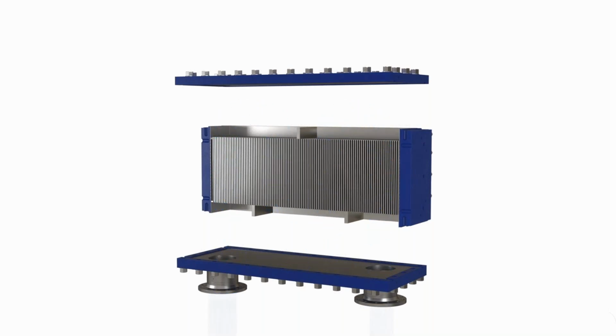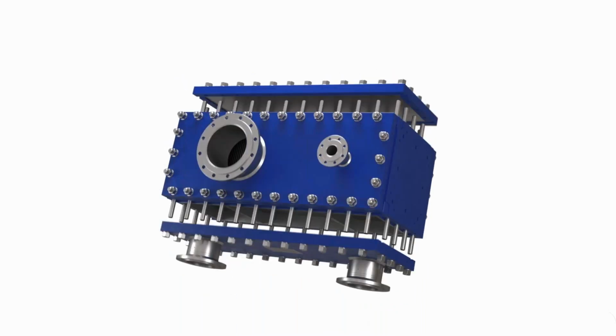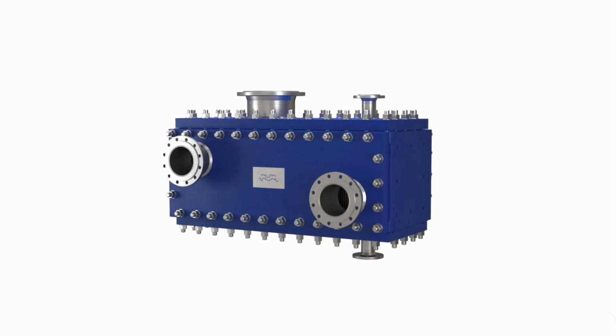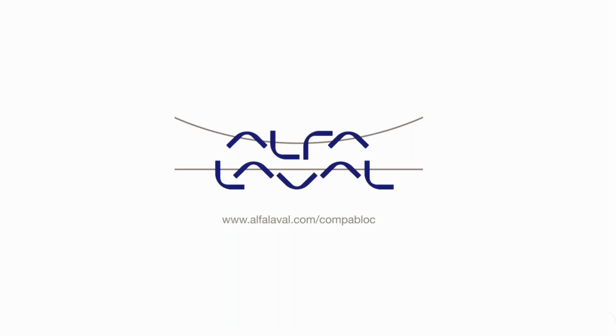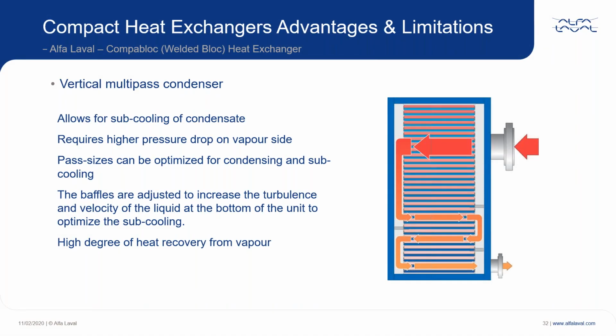There are many more variants, but I won't bore you with all the videos there. And most of them are available on YouTube if you really want to go and have a look. So we can do a multi-pass vertical condenser. This unit here allows for subcooling of the condensate. We have the main condensing in the first pass, and as we get down to the lower sections, we subcool the condensate, and we can have a liquid level control on the bottom.